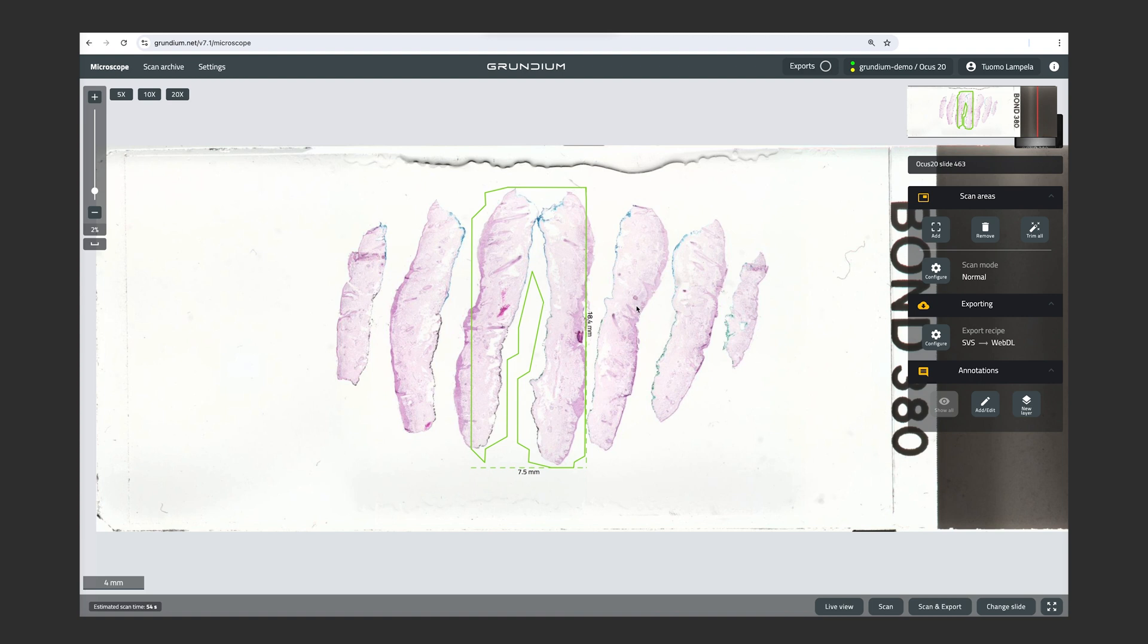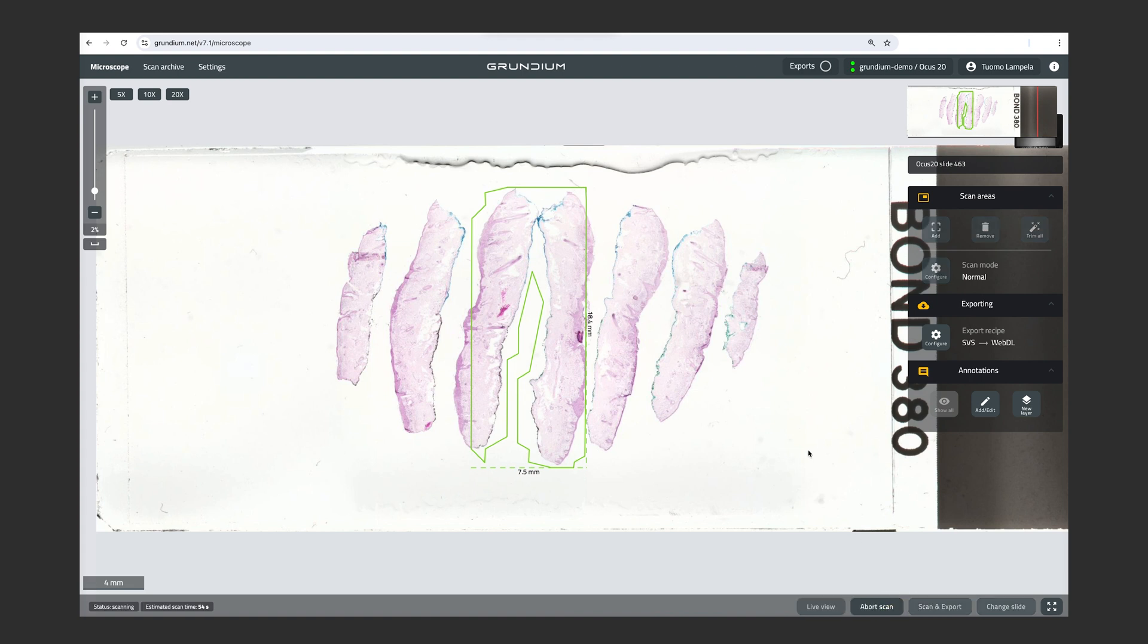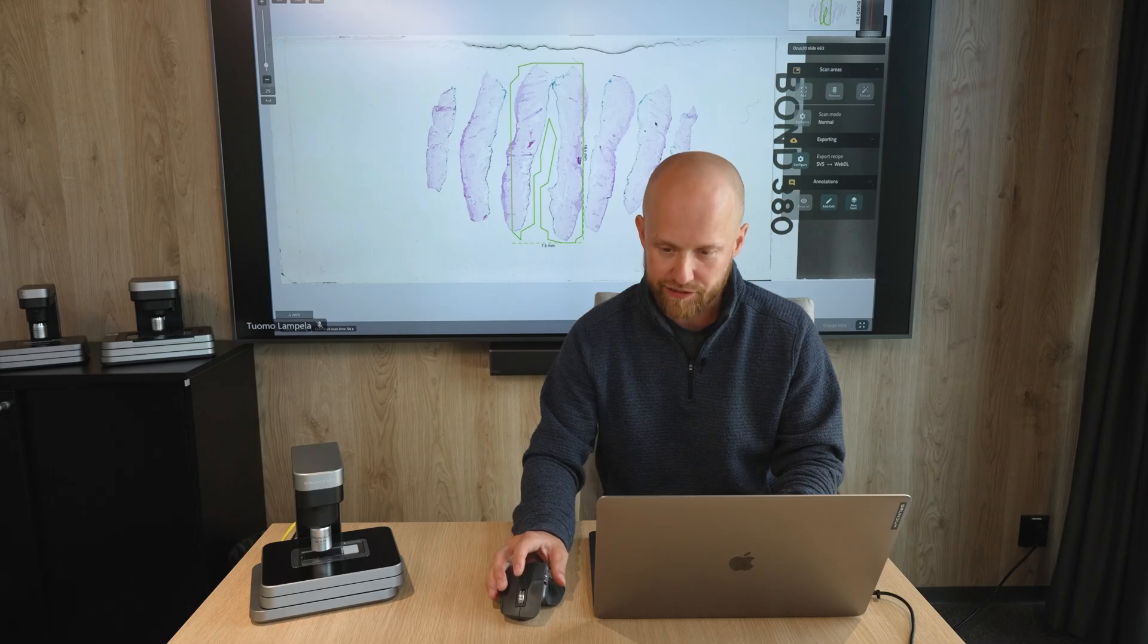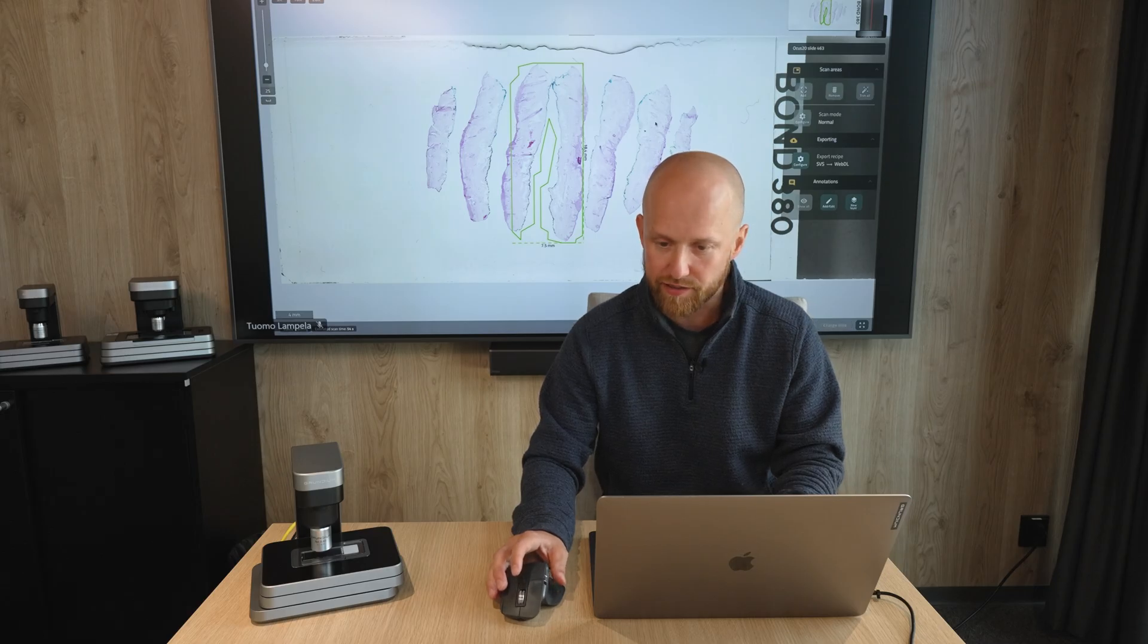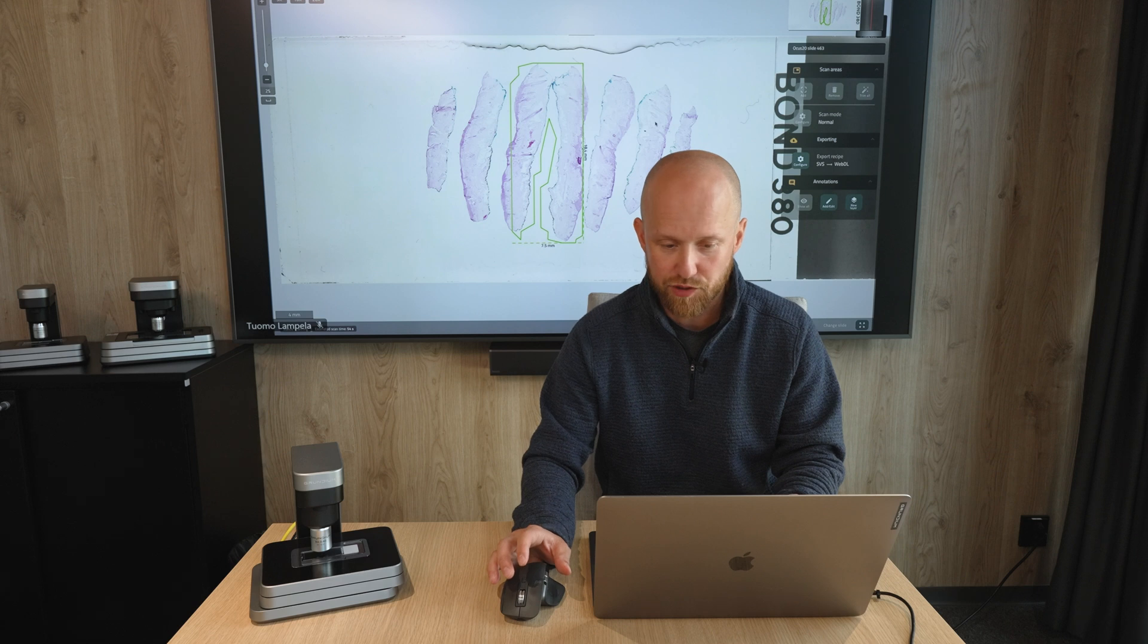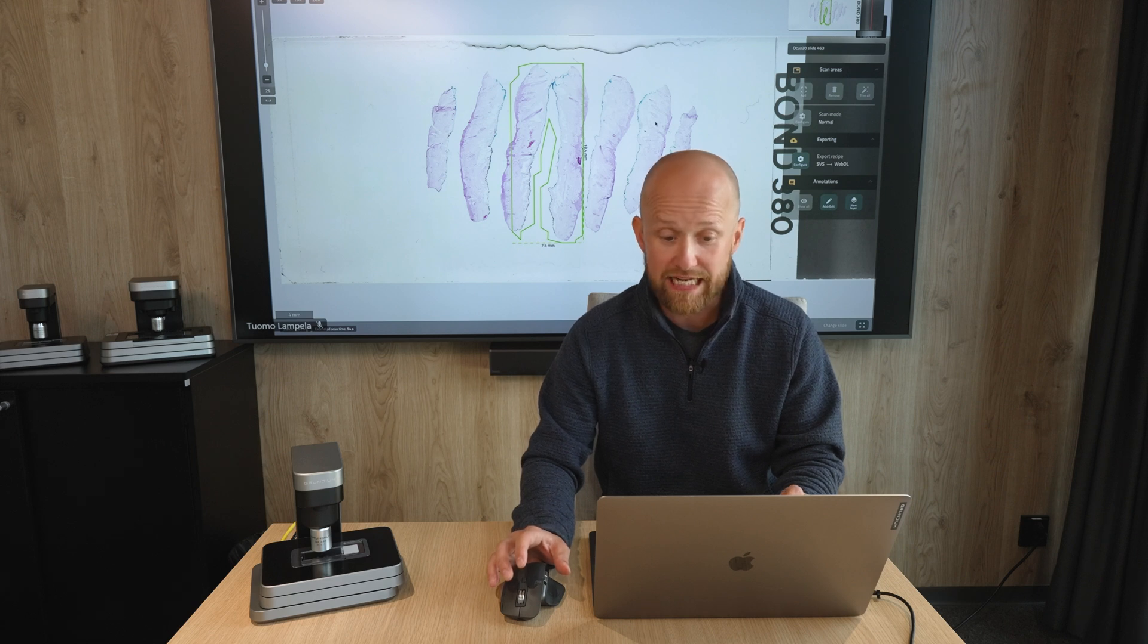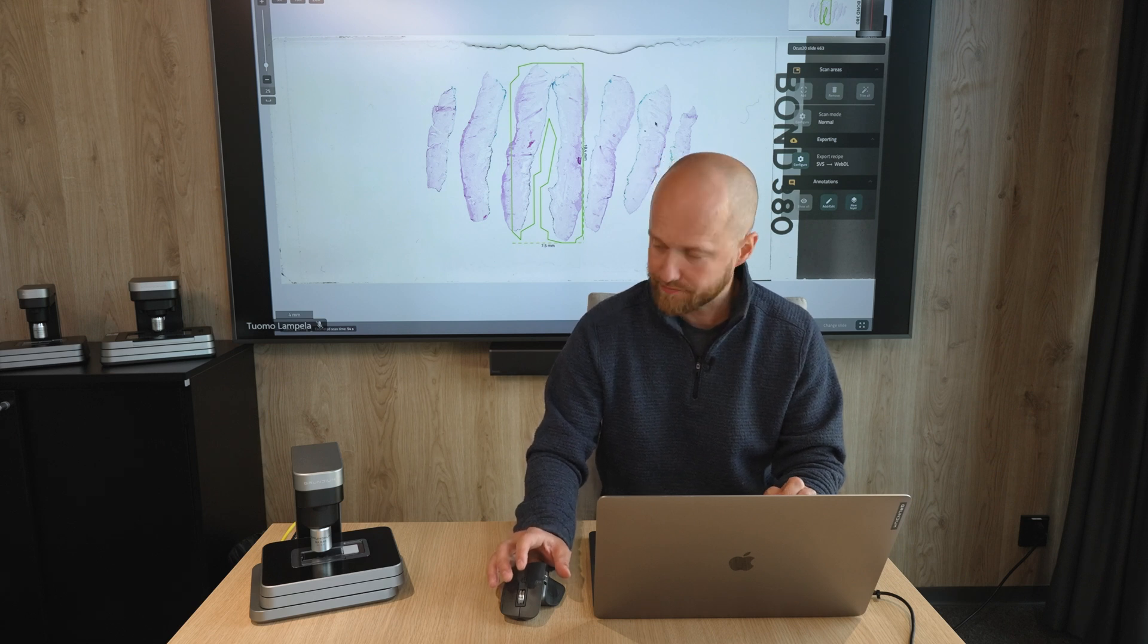And as always, we can always adjust the scan area by dragging at any point of the scan area corners or edges. And we can see that this scan area is 18.4 millimeters times 7.5 millimeters. And you can see the estimated scan time in the bottom left corner here, which is now 54 seconds. And now we can just click on Scan to scan the area with full resolution. And at this point it's the Ocus 20, so it's going to be at 20x.